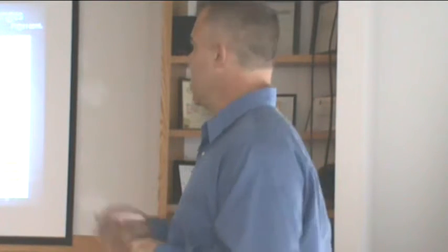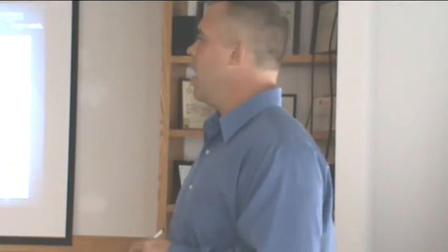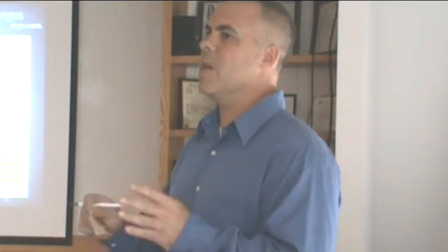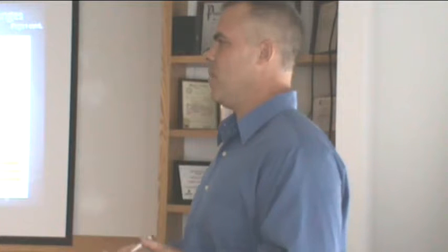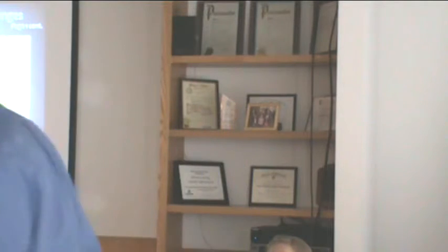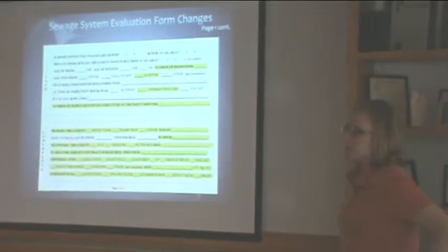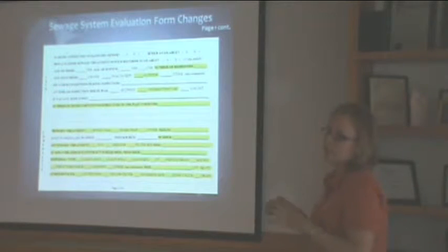So if it's a newer system, this just brings it up because every one of those has a lift tank if you're on LPP. Just be very cautious of it. And if we see it's a mound and there hasn't been a flow test or something done on it, we'll say the form is deficient. It'll have to be redone. And to add to that, I haven't had any mounds that I can remember yet, but you want to make sure you get into the control panel and put down the event counter, because when we final them, we have what the event counter is, so we can calculate back and see what it's been doing over the last few years.